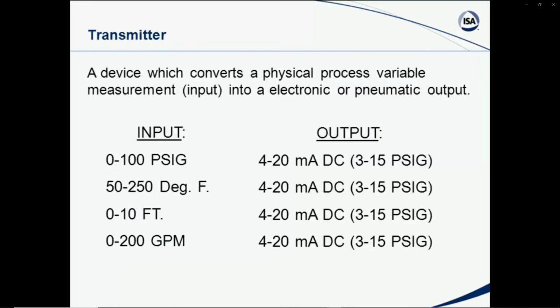What is a transmitter? Well, first of all, you could have a lot of different definitions for it, but basically a transmitter or a sensor transmitter is a device that converts some physical process variable that is a characteristic of our process into an electronic, a pneumatic, or a digital form of output that represents that particular variable. As an example, we may have 0 to 100 psig, a pressure situation that we convert to a 4 to 20 milliamps, 3 to 15 pounds, or some digital signal that may be going to our control system, which may be unique controllers mounted in a panel or on a wall or something like that, or it may be going into a programmable electronic system such as a PLC, a DCS, or what we now call, I think, programmable automation controllers.